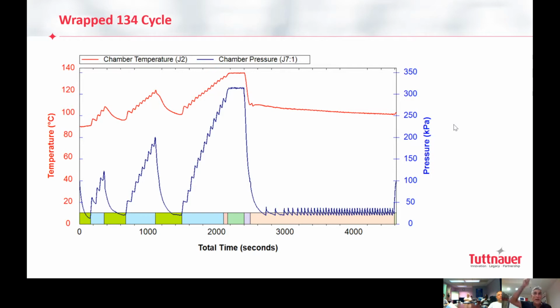And then in one pulse, let's say from 0 inch mercury, like you use, down there to less than 27 or more than 27, it means I removed 99%, correct? And then I'm okay. But in order for that, I need a very big vacuum pump and very expensive vacuum pump, which cannot fit this small machine.